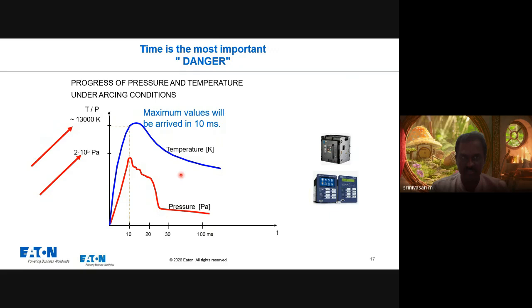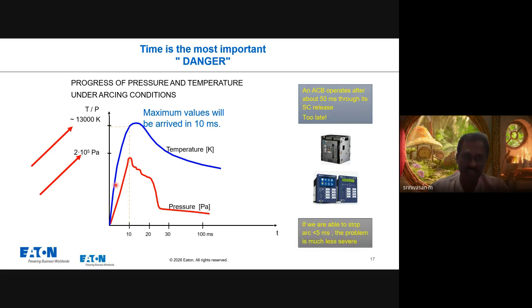Normally when an internal arc happens, if you see the graph, within 10 milliseconds it reaches the highest temperature. So the point here is we need an arc mitigation device. We need an arc mitigation device that mitigates the arc in less than 5 milliseconds, so that we can avoid the extent of the damage, or limit the damage.